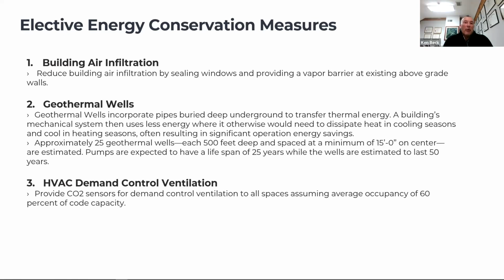So basically what we do is we monitor the CO2 in the spaces. Most control companies now make a combination temperature sensor and CO2 sensor that we can use to control the ventilation to the spaces. Again, ventilation is not our friend. It's a huge energy demand to the building if we have to design the system for full occupancy.